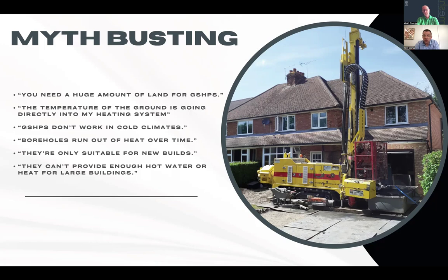We've had a few clients asking, is my hot water in the shower going to be hot enough? I always explain it this way. We will generate the hot water to about 50 degrees. You might have to blend this with some cold water to get the right temperature in the shower. I always say, think about when you go to a hotel: at roughly 38 degrees you have to press the safety button to get hotter water. So how often do you go much higher than this? And we are generating 50. If you really like hot water, you just blend less cold water with the hot water to get really hot water.